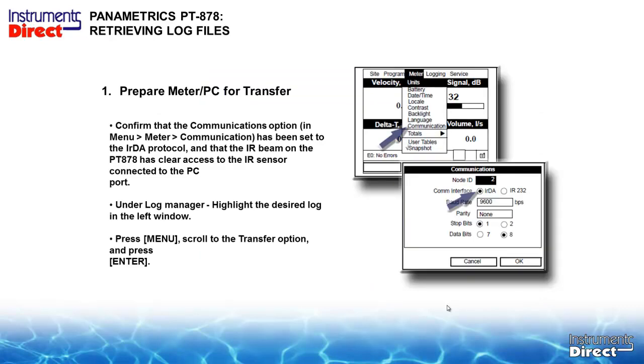So to retrieve the data, we have to confirm that the communication option in the menu, meter communications, has been set to the IRDA protocol, and that the IR beam on the PT878 has a clear access to the sensor. Some of the older devices have serial ports, and the newer devices have USB ports.